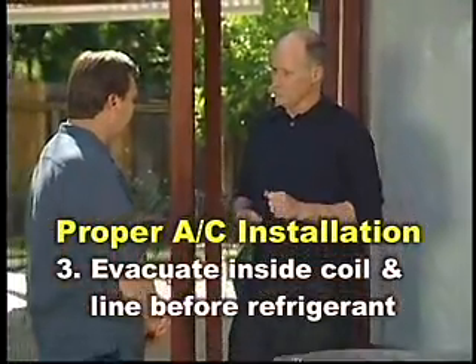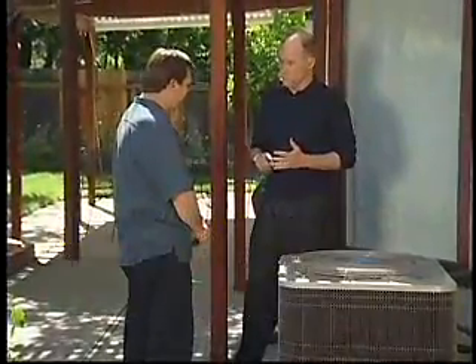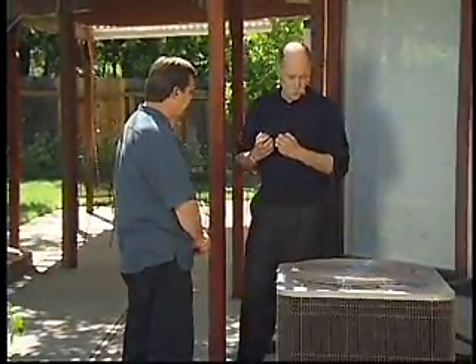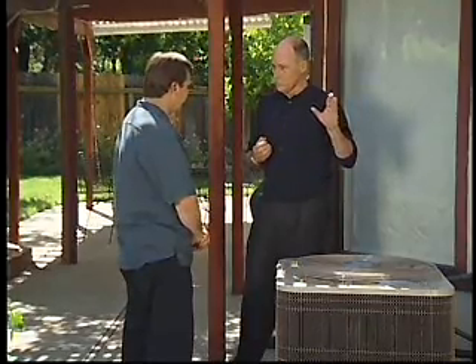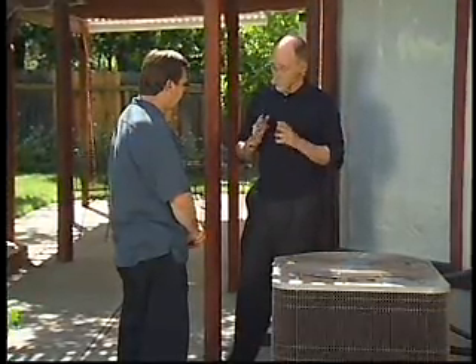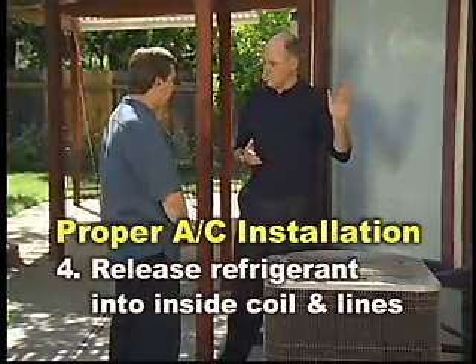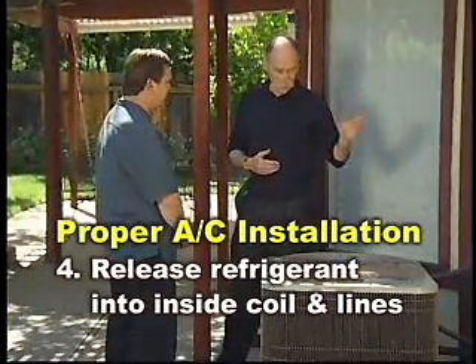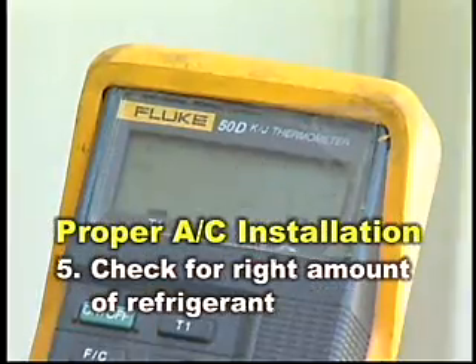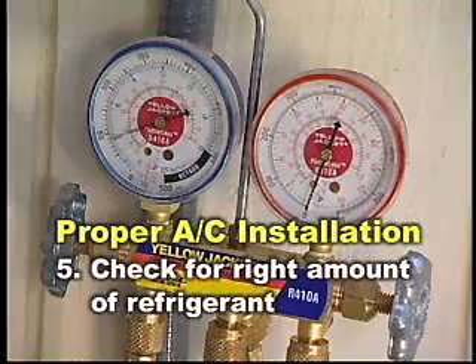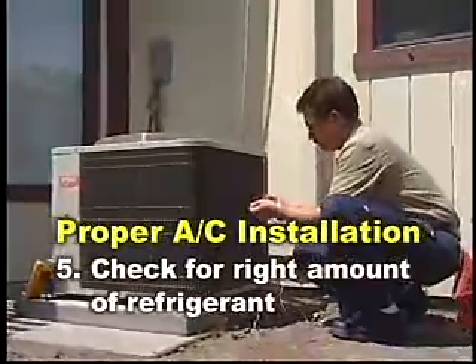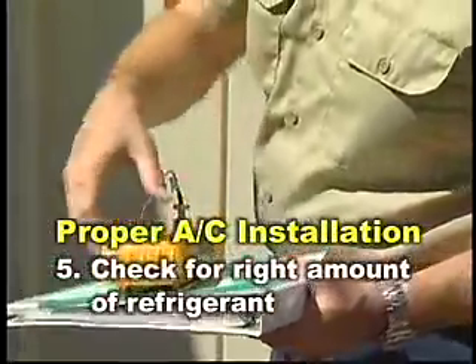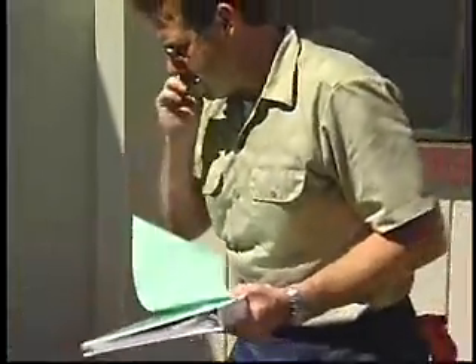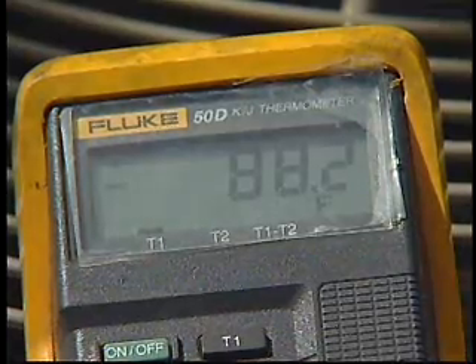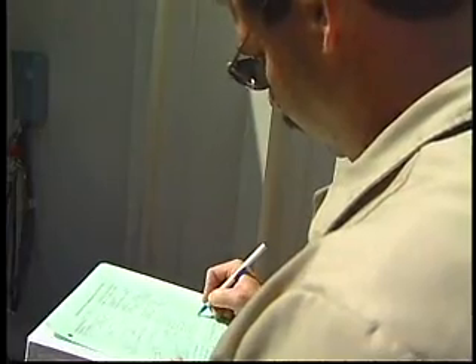Next thing you have to do is evacuate the lines and the inside coil. So you need to use a vacuum pump, you need to use a micron gauge, you need to pull all the moisture and air out of those lines and that inside coil before you put the refrigerant in. Then the next thing you have to do is release the refrigerant into the inside coil and the lines, and then you have to check to make sure you've got the right amount, because this comes with a certain amount, but it's not necessarily the right amount for your inside coil or the length of the lines that you actually have. So you usually have to add enough refrigerant to get it up to the right amount in order to have the unit run at its top efficiency.